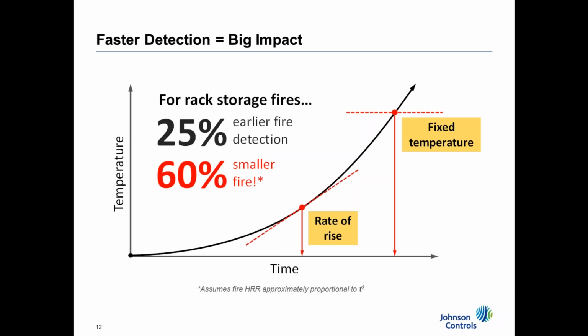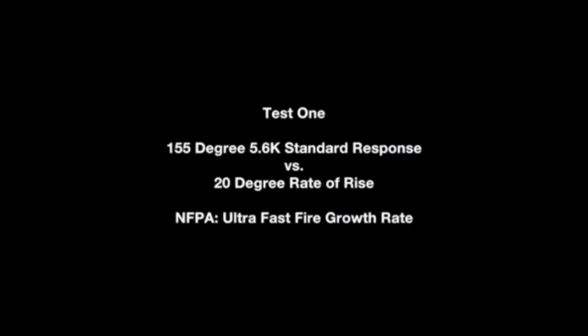If you're waiting for a fixed temperature, especially in a large facility where you're 40, 45 foot in storage, it takes a while for that fire to build up through the racking system to reach that temperature and across the ceiling in that T fashion. And so you're more than likely going to activate more sprinklers than you would normally want to activate.